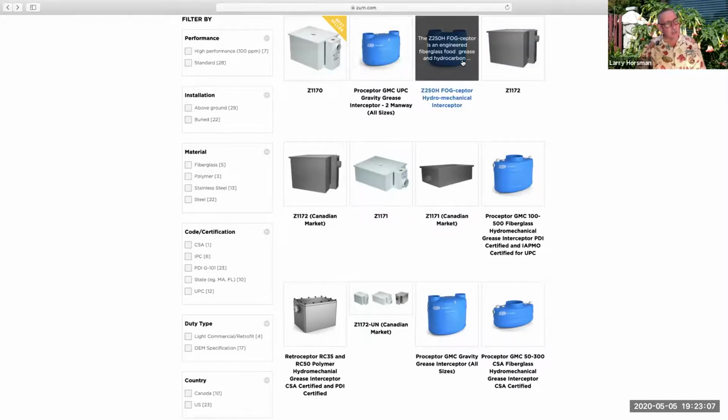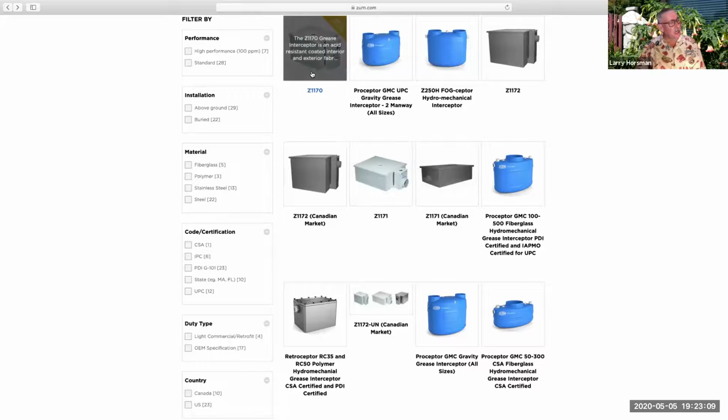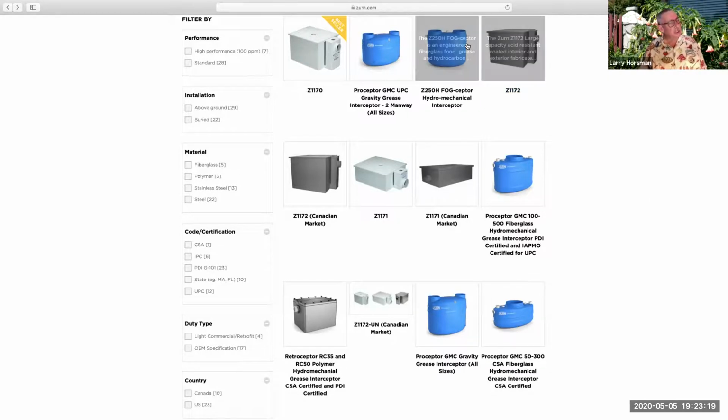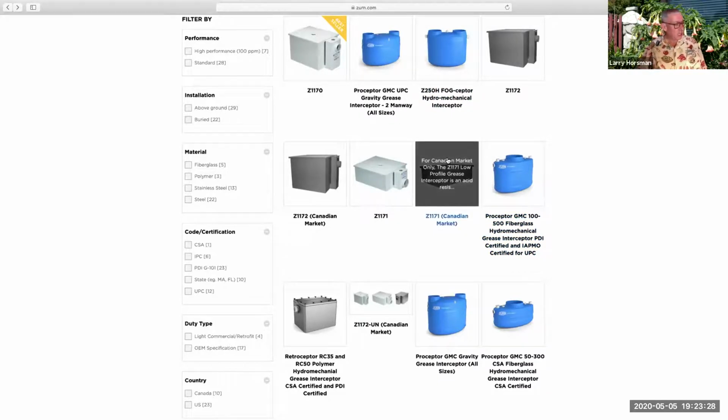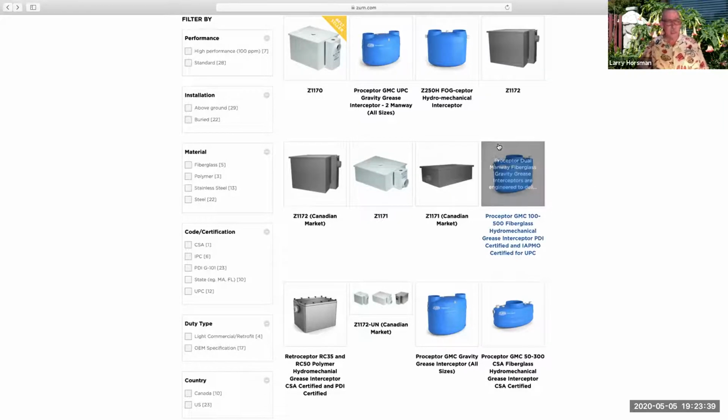And some of these are plastic, and some of these are epoxy coated metal. So there are different materials out there, different sizes. Some of them have, you can see this is very similar to a septic tank, with the access holes at either end, and you may need access holes. So some of them are designed to go into the ground in a parking area, some of them in a non-parking area. They have to be constructed a little bit differently, and so do the lids.